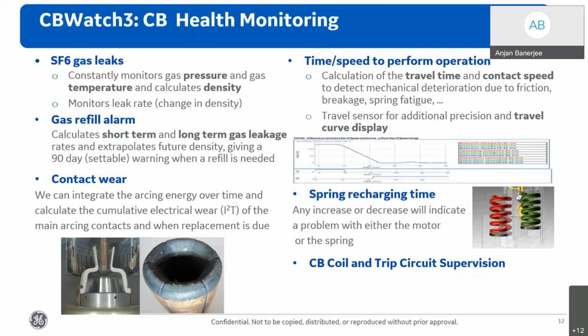This can be done in two ways. The best way is to mount a position sensor in the mechanism. In that case, the travel time and the speed can be computed precisely. Over and above, the device can also plot the travel curve of the circuit breaker contact, as you can see over here. If, for example, a position sensor is not available, the device would compute the travel time or the speed from the auxiliary contact of the circuit breaker. Next, the device also computes the spring charging time. If the spring charging time is too high or too low, both are problematic, and that would point to a problem either in the spring or in the motor of the circuit breaker.